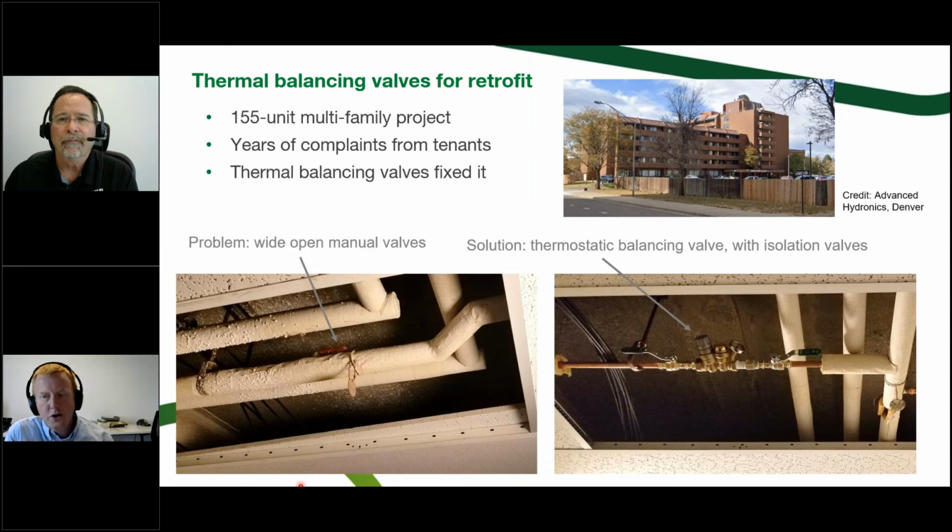The one thing that I'm always cautious of, though, especially when you're mixing and matching different types, is I usually recommend sticking with the same type of valve if you've got an existing building. It doesn't necessarily have to be the same brand, but if you've got existing static manual balancing valves, going with that in the addition. The reason being is that if you have a dynamic valve like a thermal balancing valve, and you've got fixed speed circulators and manual static balancing valves, as the thermal balancing valves open and close, it's going to change the dynamics in the rest of the system, which could increase or decrease flow to those existing circuits. And in those scenarios, there's no way to actually balance those manual balancing valves properly when you've got a side over here that's just doing whatever it needs to do. It's going to do a great job on the thermal side, but then the existing side is going to be like, hey, I'm either starving or I've got too much.